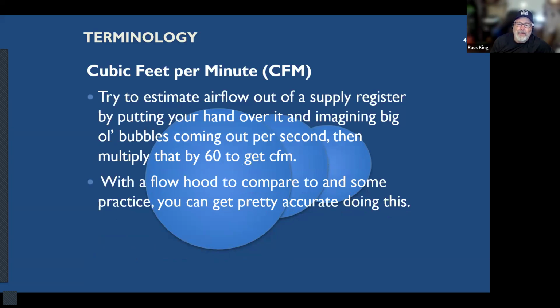So try to estimate the airflow out of a supply register by putting your hand over it, and imagine how many bubbles are coming out per second. Put your hand over a register and feel it, and imagine these 15-inch diameter bubbles forming on this register, and just count how many you think there are per second, and then multiply that times 60, and you get pretty darn close.